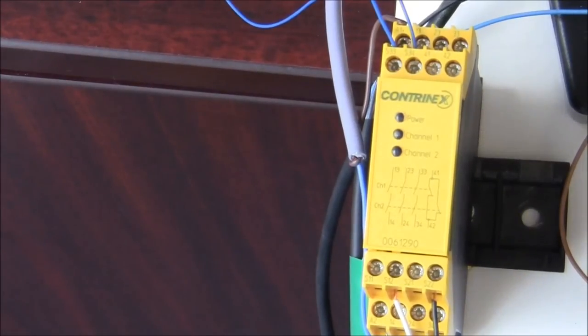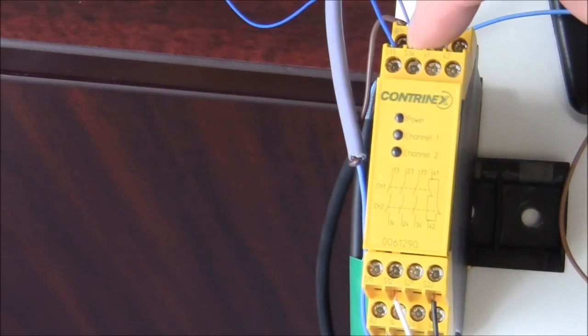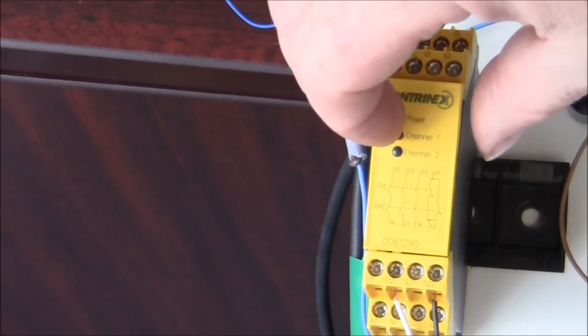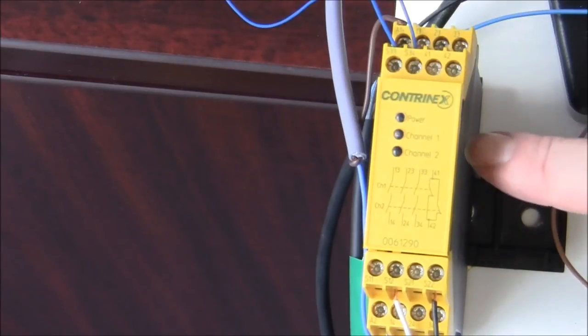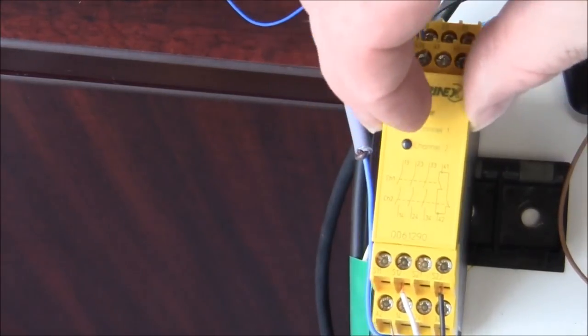Going from automatic restart mode to manual mode is very simple. Instead of going between S33 and S34 with a jumper wire, we're going to break that with a switch. There will be a switch on your panel that you would just depress when you want it to restart. When you do that, you have to pry this panel up. You just simply put a screwdriver in right here, twist it, and this will come up.